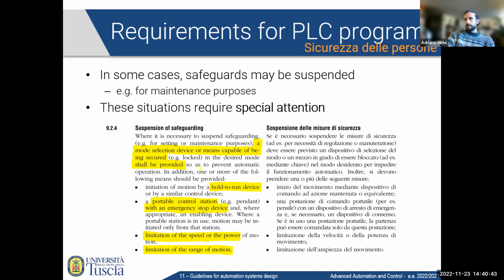Again, when it is necessary to suspend safeguarding, a mode selection device or means capable of being secured in the desired mode shall be provided, so as to prevent automatic operation. In addition, one or more of the following means should be provided: first, a hold-to-run device or similar control device.